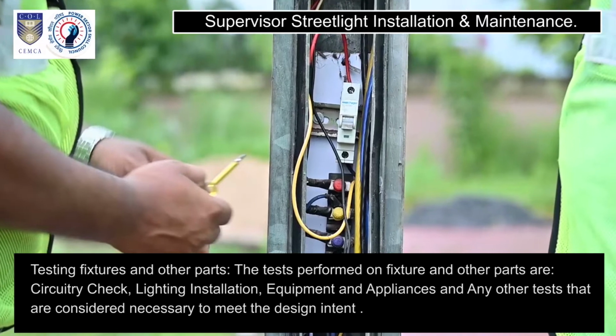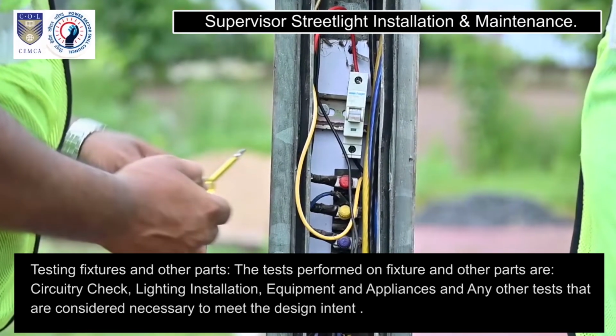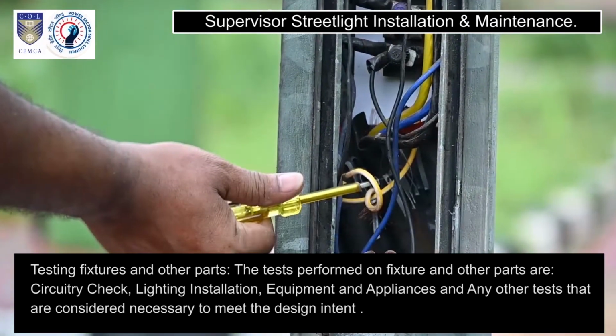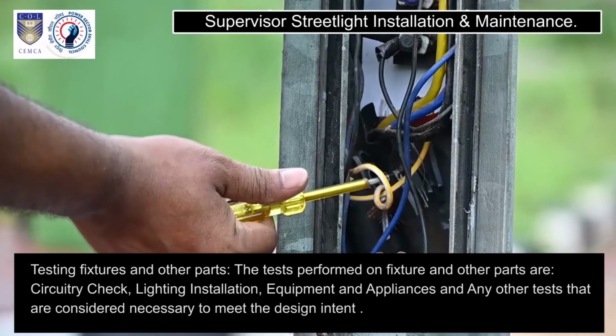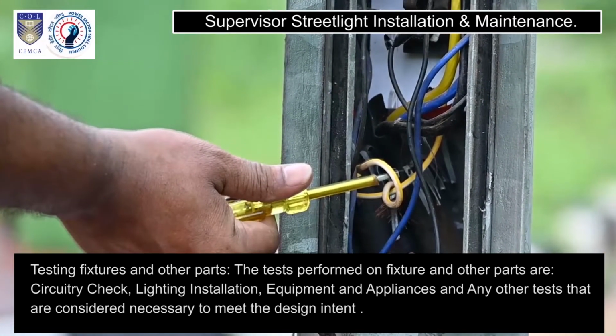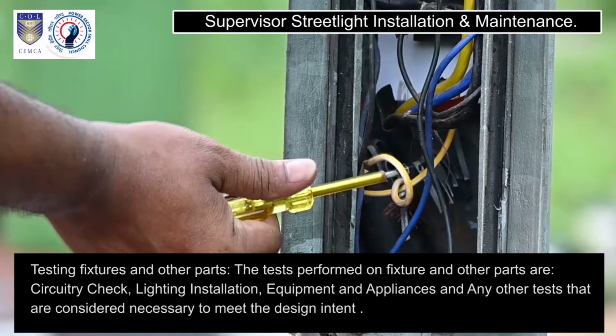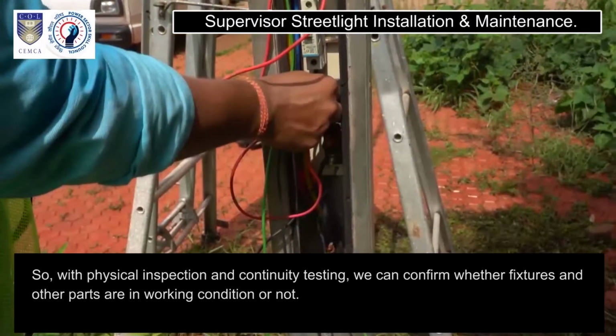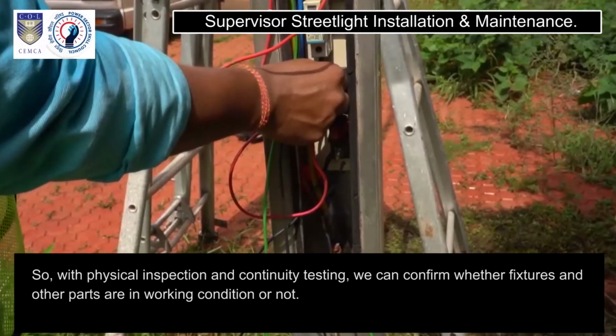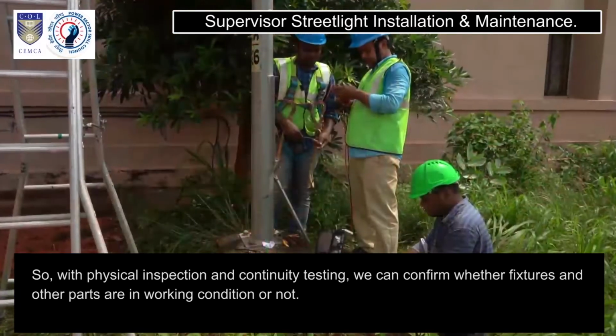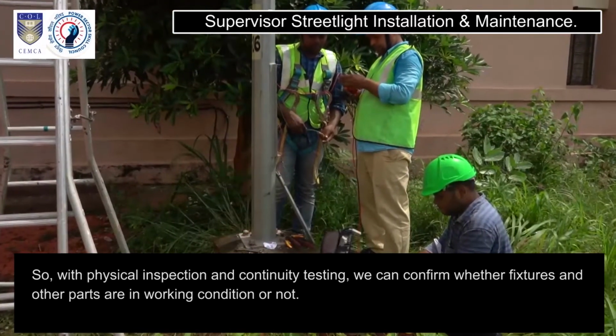Testing fixtures and other parts. Tests performed on fixture and other parts are circuitry check, lighting, installation, equipment and appliances, and any other tests that are considered necessary to meet the design intent. So with physical inspection and continuity testing, we can confirm whether fixtures and other parts are in working condition or not.